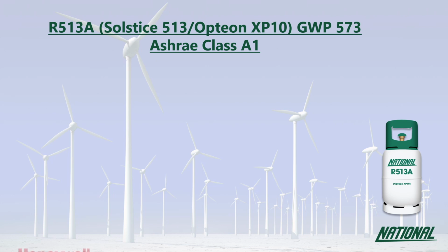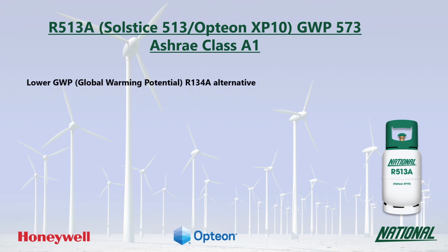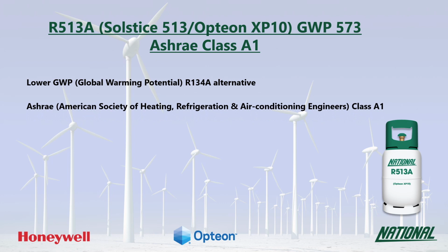R513A was developed by Honeywell and Chemours as a lower GWP R134A replacement. You may also see it referred to by its manufacturer's trade names, Solstice 513 and Opteon XP10. Its GWP is 573, which is low to medium, and at less than half the GWP of R134A, it is a much more environmentally friendly option, classified by ASHRAE as A1, non-flammable.